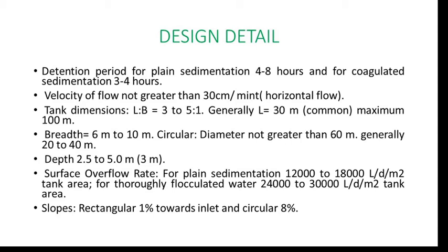During this consideration of depth of the sedimentation basin, the sludge depth is also considered, and the sludge depth is taken as 25% extra. The next one is the surface overflow rate. For plain sedimentation it is 12,000 to 18,000 liter per day per meter square tank area, and for flocculant it is 24,000 to 30,000 liter per day per meter square of tank area.